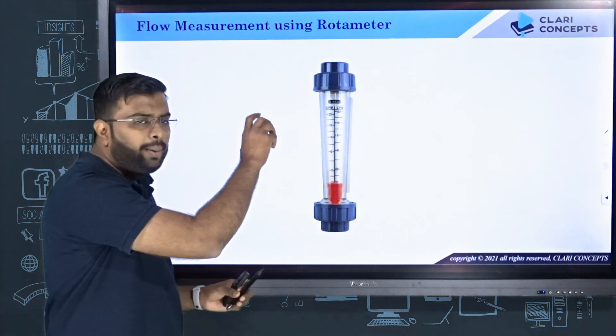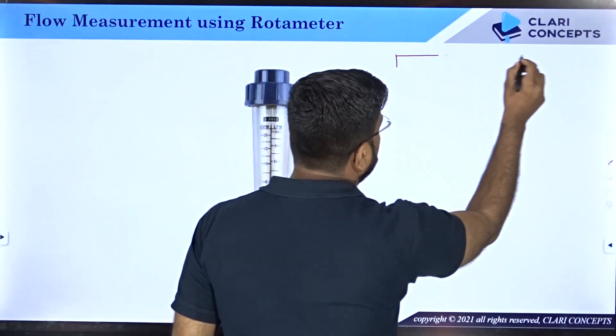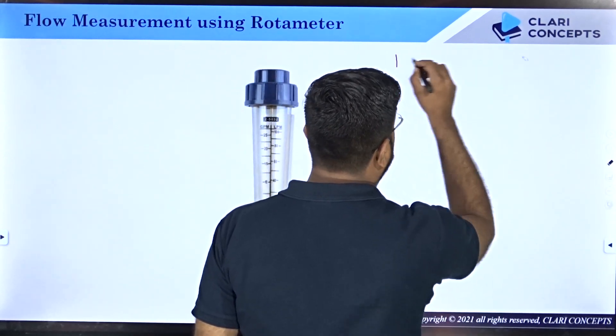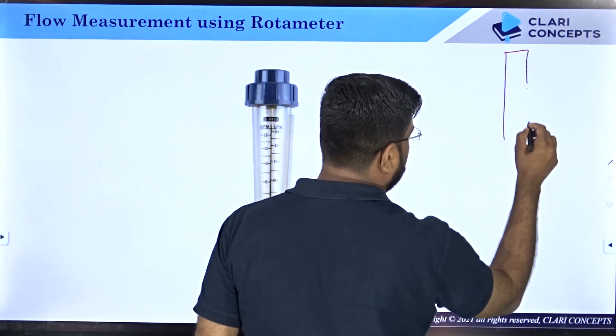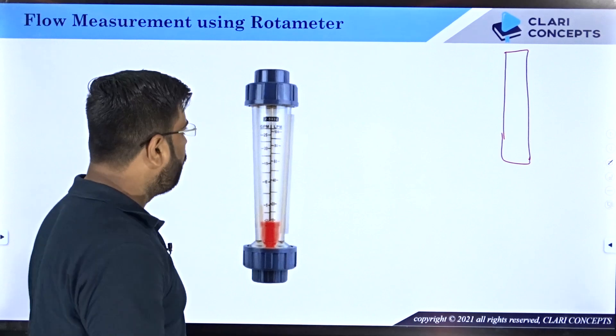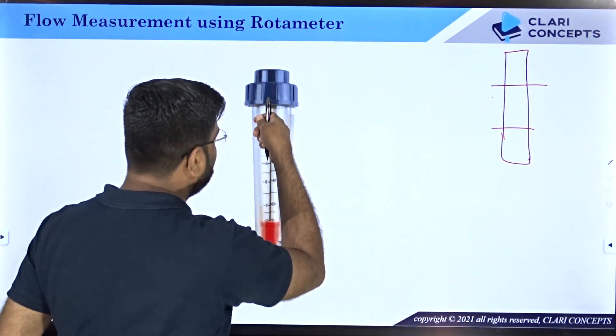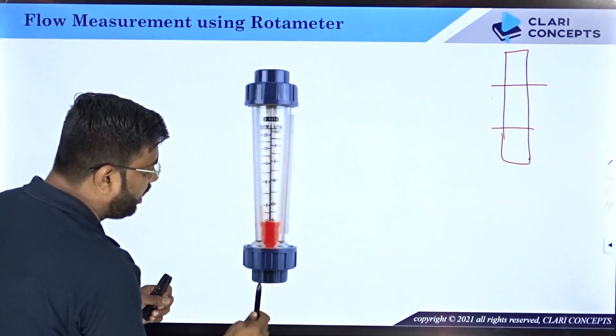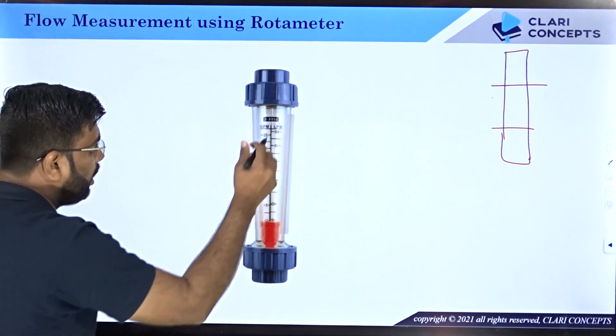To install a rotameter, you take the pipe where the flow rate is to be measured, cut a portion of it, and insert the rotameter in its place. The condition is that the rotameter must be installed in a vertical length of the pipe. The bottom of the pipe connects to the bottom of the rotameter and the top connects to the top, so fluid flows through the rotameter.